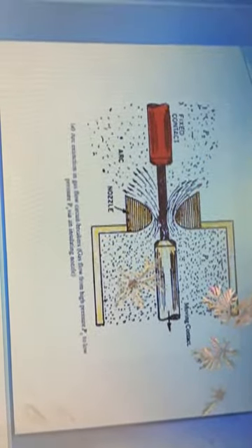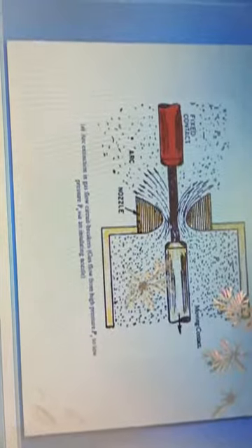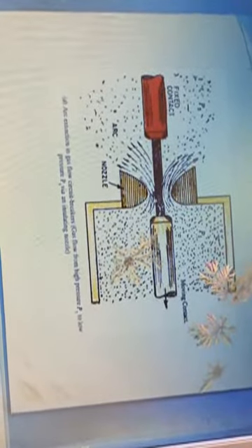This trapped gas is released through the nozzle, and during the arc extinction process, with the travel of the moving contact and movable cylinder, the gas puffs over the arc and reduces the arc diameter by axial convection and radial dissipation. Then at current zero, the arc diameter becomes too small and the arc is extinguished.